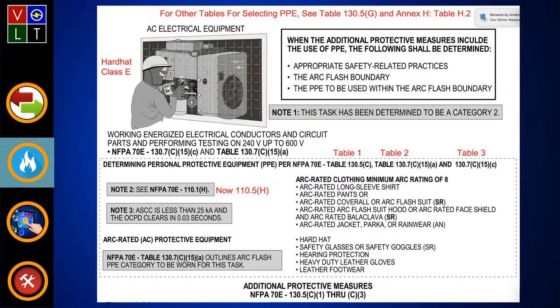Now we went over the boxed in information. Now that we can use the table, that's one way, our table 130.5G, and just use that table under those conditions. Or we can drop down and use, as you see in the illustration, table 130.5C. That's the first table. You go through that, look at your job tasks, fall into the parameters there, and then you can determine if you need equipment or not. If yes, then you would go to the next table, which is table 2, 130.7C15A for AC, and B for DC. And then you would get your category based upon the task that you selected from your first table, 130.5C.